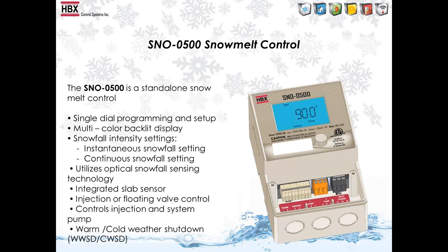So the Snow500, when we developed it, basically took 90% of our Snow-1000 sales, because at that time people were not looking for the big snow melt systems anymore. They were looking for something that just basically gives a boiler on-off output to talk to some condensing or modulating boiler system, or a larger system where it can just turn on a pump at that point. So the Snow500 is still a standalone control. It doesn't need any modules. It doesn't need anything extra. It's just the Snow500 is what you need for the snow melt system. Obviously you still need the sensor, but as far as controls, it's just the Snow500 only.